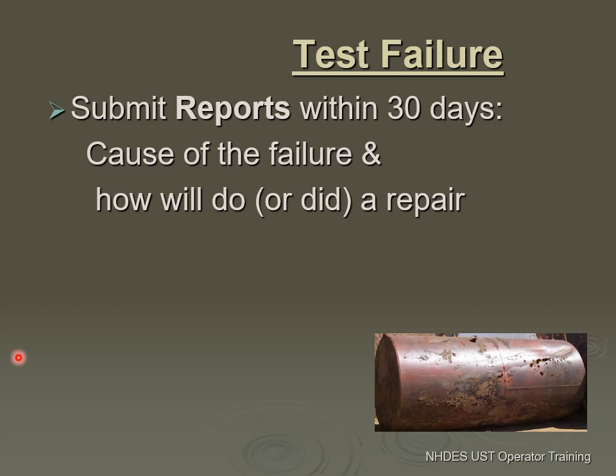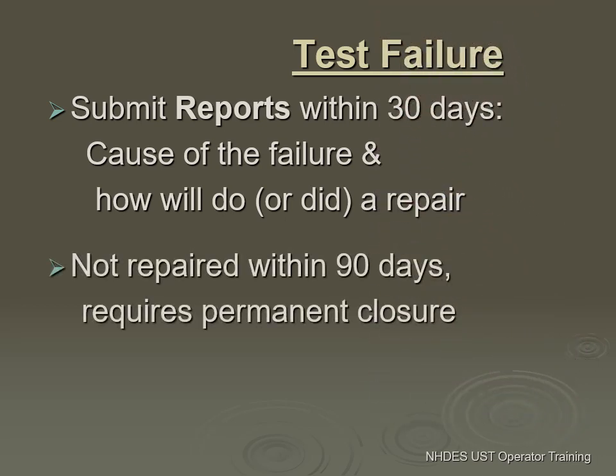If your test fails, within 30 days you want to submit to the state: it failed, here are the results, and what are you planning to do — or have you already repaired it? I need that within 30 days. If it's not repaired within 90 days, on the 90th day, permanently close the tank and remove it from the ground. You cannot operate an underground tank that has a failed corrosion protection system.